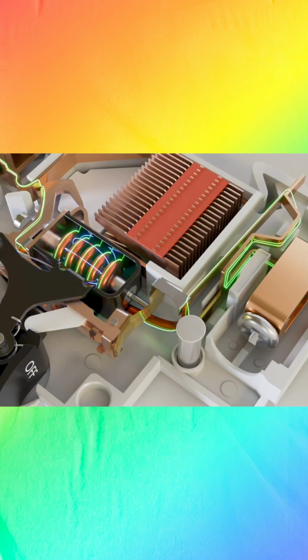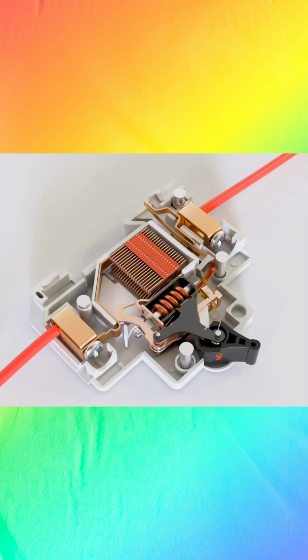A bimetallic strip is a component made up of two different metals bonded together. These metals have different coefficients of thermal expansion. It means that, when these metals are heated, they expand at different rates. When an overload current passes through bimetallic strips for a few seconds, it generates excessive heat in the bimetallic strip. Due to this excessive heat, a bimetallic strip bends and triggers the operating mechanism.